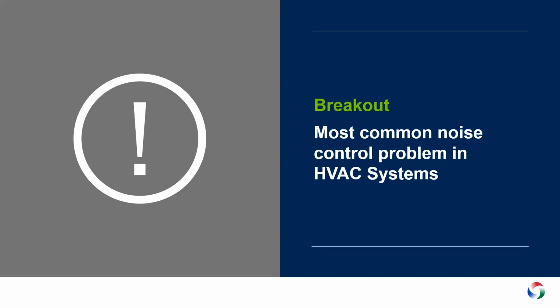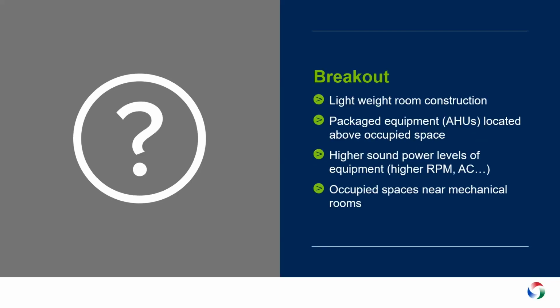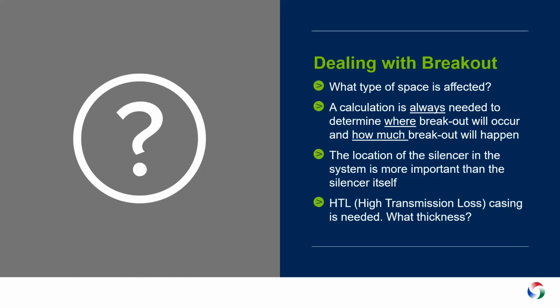So breakout is the most common noise problem in HVAC systems, and the reasons behind that are lightweight room construction, the air handling unit located above the occupied space, higher sound power data of the equipment, and the occupied spaces near the mechanical room. And how to deal with the breakout noise, we will always look into what type of space is affected, and the calculation is always needed to first of all calculate to see will there be a breakout noise issue, and if there is, how much. And the location of the silencer plays a very critical role. And then based on the calculation, we also find out, do we need an HTL casing or we don't?